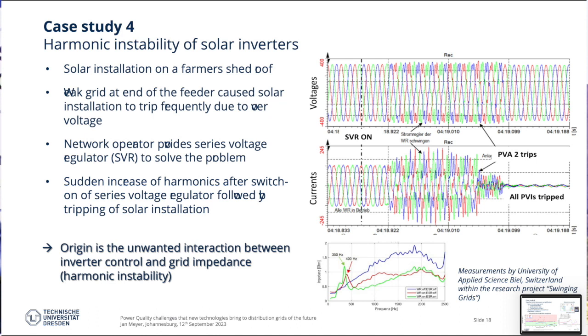The network operator wanted to do something really good for him and installed a series voltage regulator, which is equipment that basically steps the voltage a little bit down so that there is more that can be injected by him. What finally happened is that he did not trip with overvoltage anymore, he tripped with excessive harmonics. He said, well, that was not the solution that I wanted to have.